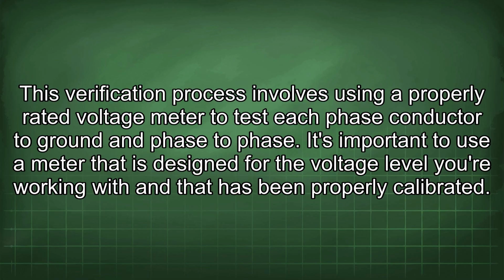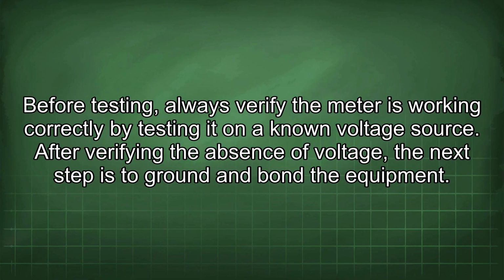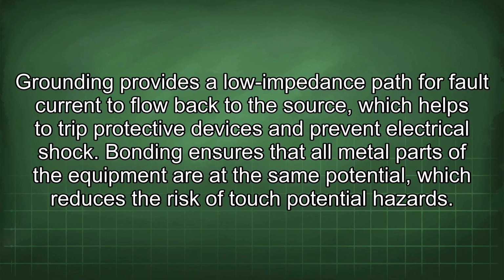It's important to use a meter that is designed for the voltage level you're working with and that has been properly calibrated. Before testing, always verify the meter is working correctly by testing it on a known voltage source. After verifying the absence of voltage, the next step is to ground and bond the equipment. Grounding provides a low impedance path for fault current to flow back to the source, which helps to trip protective devices and prevent electrical shock.